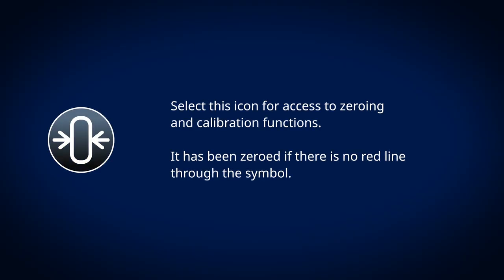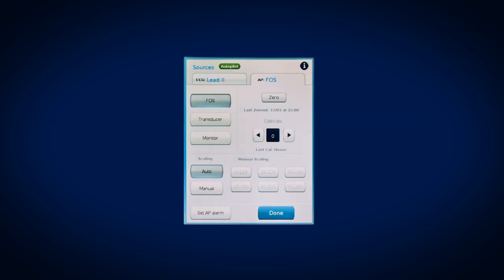The 0 symbol indicates the 0 status and access to zeroing and calibration functions. The current source of the arterial pressure displayed is identified, and it has been zeroed if there is no red line through the symbol. It is recommended that for optimal results to zero the fiber optic sensor prior to IAB insertion. Failure to properly zero the fiber optic sensor may affect the accuracy of the AP fiber optics.